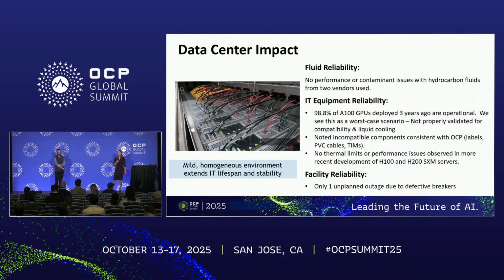At the overall data center level, we also see a significant impact. One reason I'm excited to be here is we've been operating this for 3 years. That flat line from the previous slide is complemented by data Andy will share later in the talk. We've had an amazing experience with immersion - it's fairly low complexity for us. We've had no issues at all with the fluid, with any contamination, aging, or deviation of properties over time. These fluids are formulated for much harsher environments.